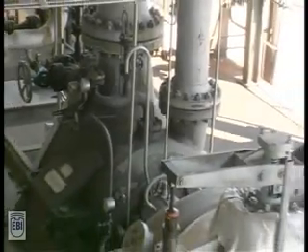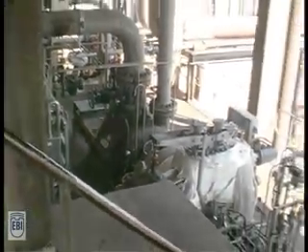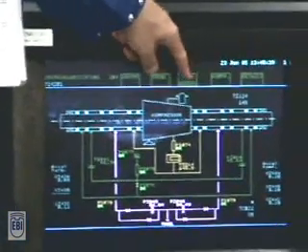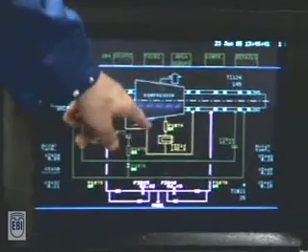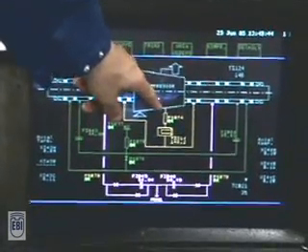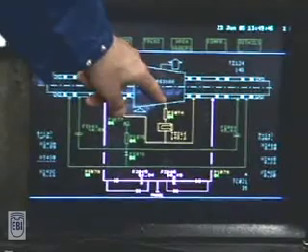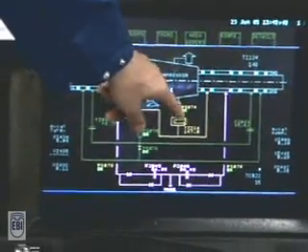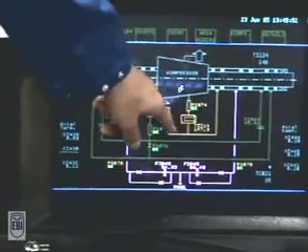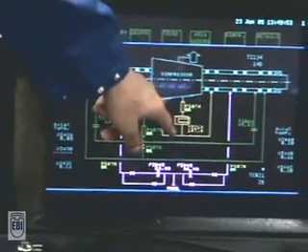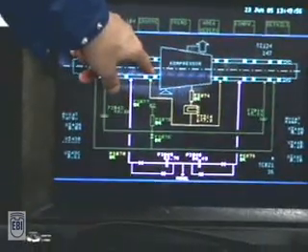The flow of the buffer gas through the sealing system. Our tandem seal with intermediate labyrinth. This shows the source of higher pressure for the flushing gas supply. At this point gas is taken off, passes a heater and a filter not shown here, and finally flows through an orifice to the gas seal.